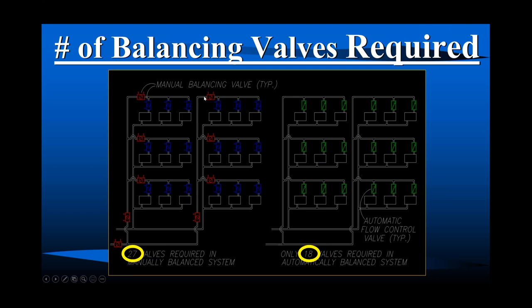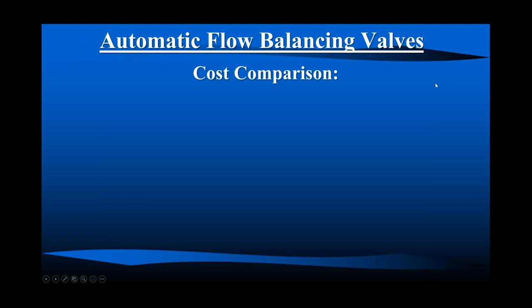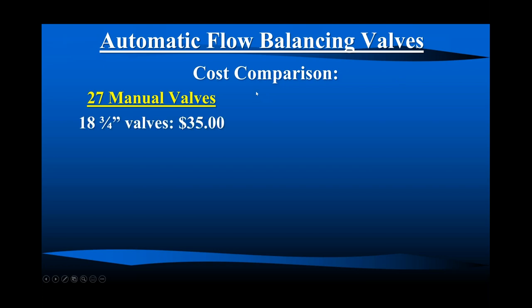Those valves have to go in there, and you have to offer access to them and the like. So let's take a look. There should be access at the terminal unit. Usually have a cabinet of some sort right next to the terminal unit or right next to it. So let's take a look at pricing now on that. So cost comparison, looking at the system, not just unit to unit. So 27 manual valves, right?